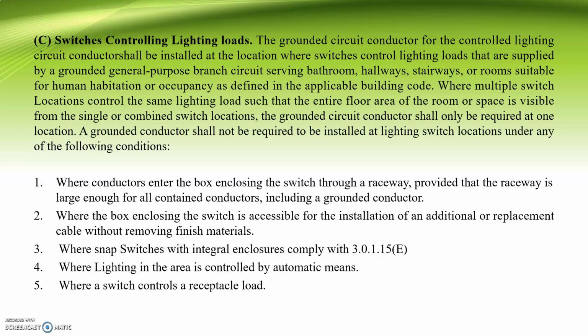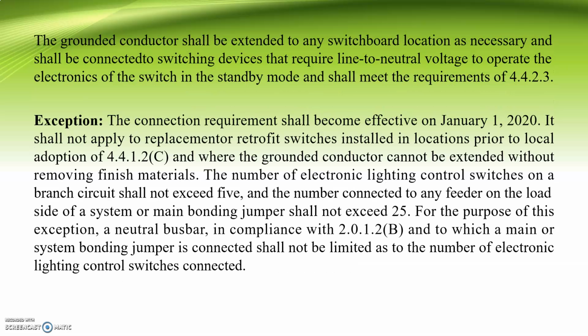A grounded conductor shall not be required to be installed at a lighting switch location under any of the following conditions. So first, where conductors enter the box enclosing the switch through a raceway, provided that the raceway is large enough for all contained conductors, including a grounded conductor. The second is where the box enclosing the switch is accessible for the installation of an additional or replacement cable without removing finished materials. The third is where snap switches with integral enclosures comply with chapter 3.0.1.15e. Fourth, where lighting in the area is controlled by automatic means, and the last is where a switch controls a receptacle load.